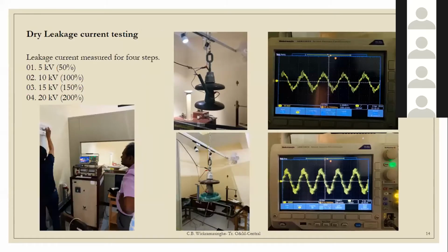First, one insulator disc. This is a disc. The rated voltage is 11 kV, which is an RMS value, 3-phase. So in order to find the optimum value, we have to take the peak value, so we multiply it by √2, and we also have to find the single phase value, so we divide it by √3. The approximate value is 10 kV, the rated single phase insulator peak value. In 4 steps, 100% means 10 kV, 50% of that is 5 kV. Likewise, I applied these 4 steps of voltages up to here.